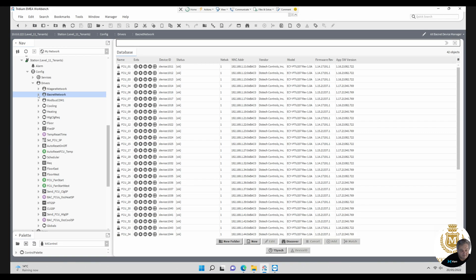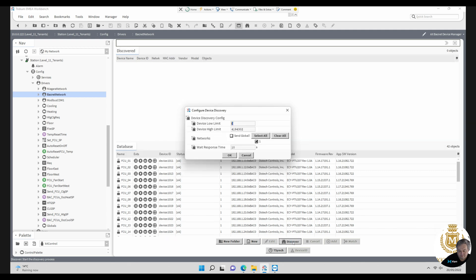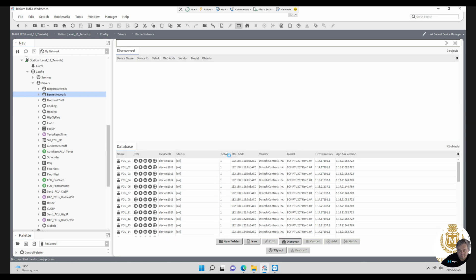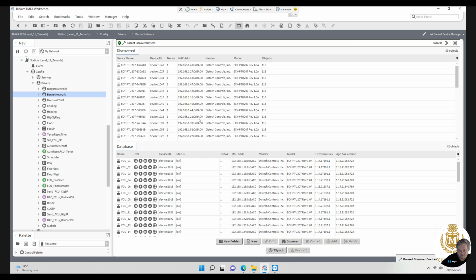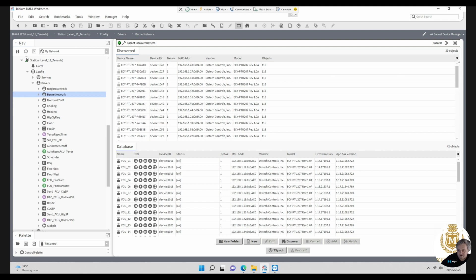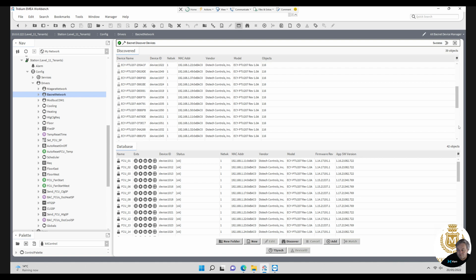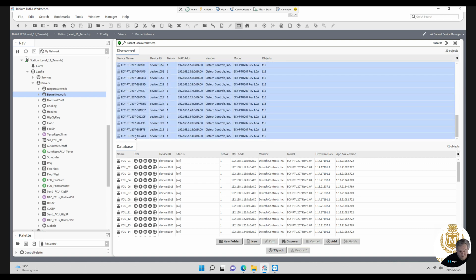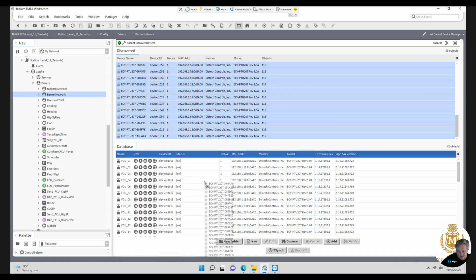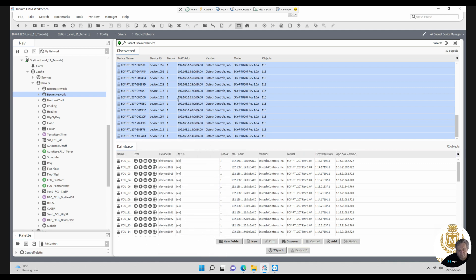This is a site with BACnet fan coils and what you would normally do if there was no fan coils here, you can just click on discover and here will be discovered all the fan coils on the BACnet network. If they're greyed out, that means it's already been discovered. There's 39 fan coils, so you've discovered 39 fan coils as easy as pressing the button. Then you would highlight all the 39 fan coils by pressing the shift key down and drag them across to the bottom.